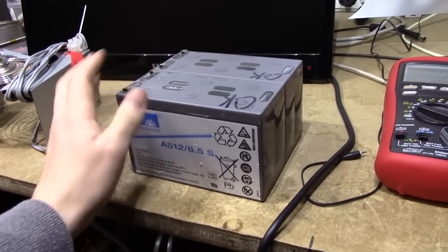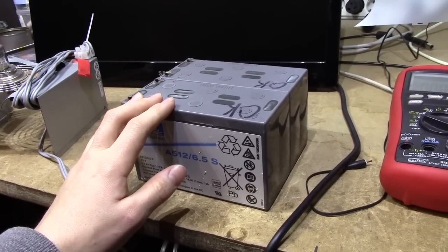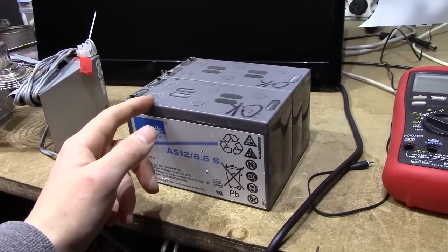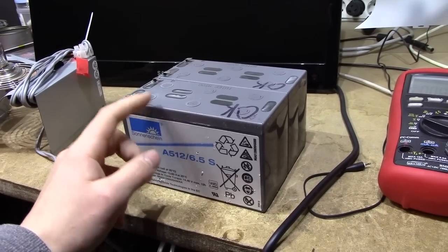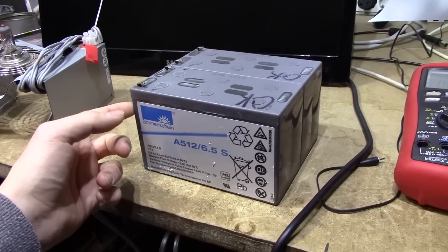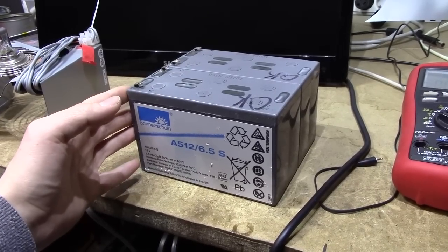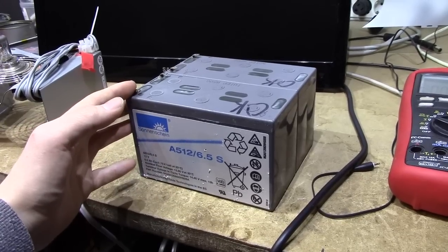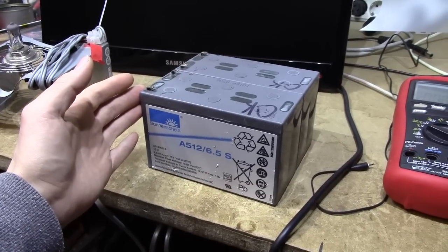That was many years ago, and I didn't use the UPS because a couple of batteries didn't work. But I believe 10 of them did work to an extent that would allow them to be used in various applications. Which is already very impressive for an AGM brick that has been allowed to be discharged to zero volts. Every single battery in that unit had zero volts or negative voltage across the terminals.